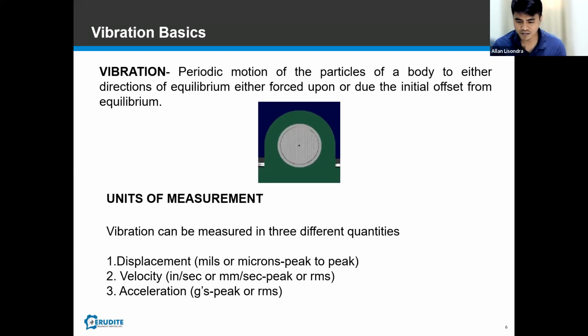In vibration, we have three characteristics. First is the amplitude, which tells us the severity or gauge of severity of our vibration. Second is the frequency, which tells us the source of vibration. Lastly, we have the phase, which tells us the time relationship between the force and the vibration, or the angular location of the shaft rotation where the highest vibration peak was measured.